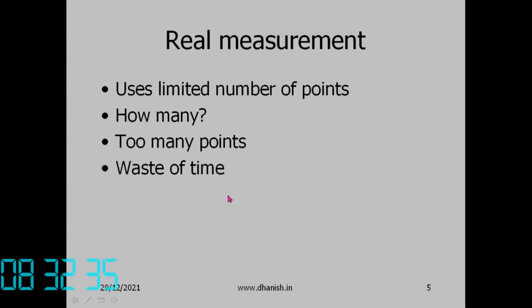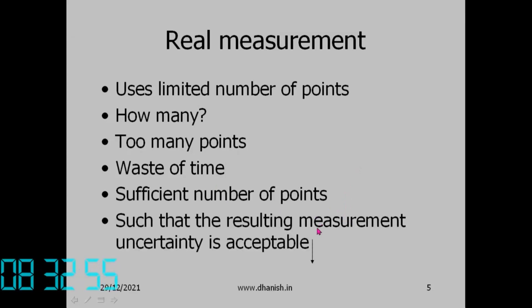Too few points is also a problem. A manufactured circle may not be perfectly circular — it may be oval or triangular. We must take sufficient points to capture the actual shape. The sufficient number of points is linked to how much measurement uncertainty is acceptable, which connects back to conformity decisions we have already discussed.